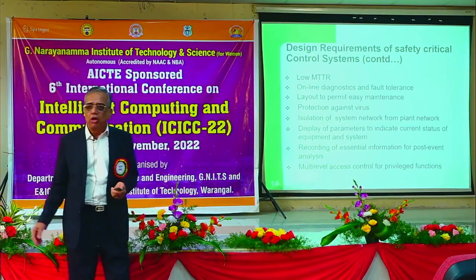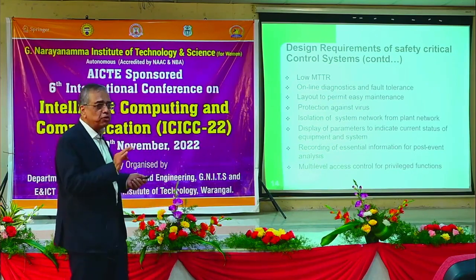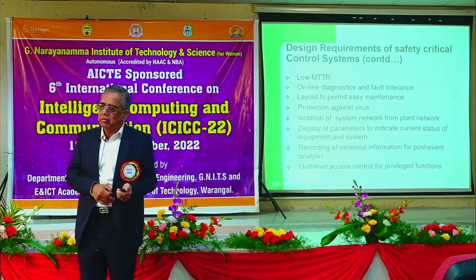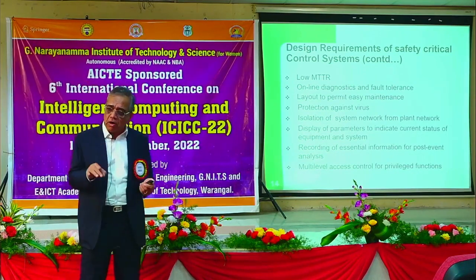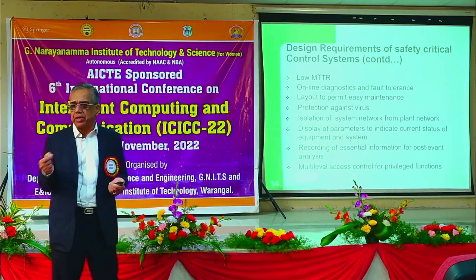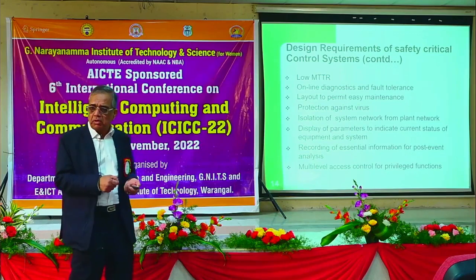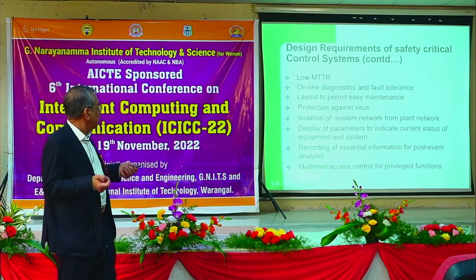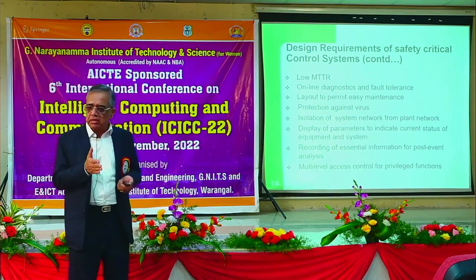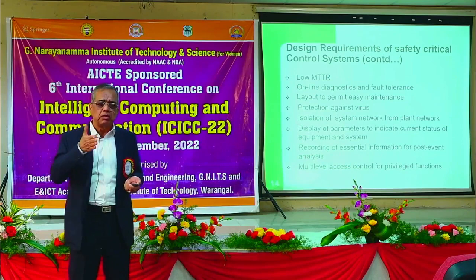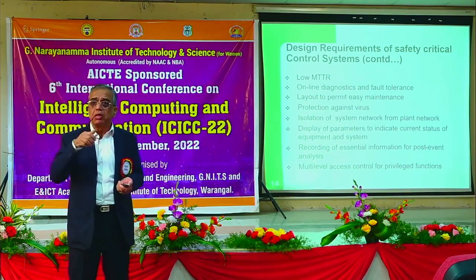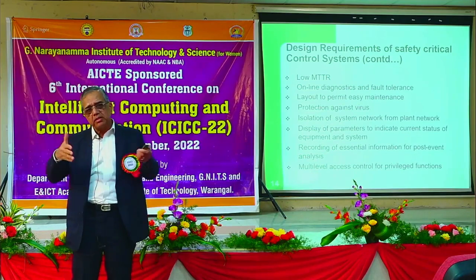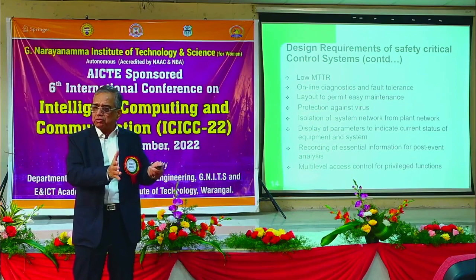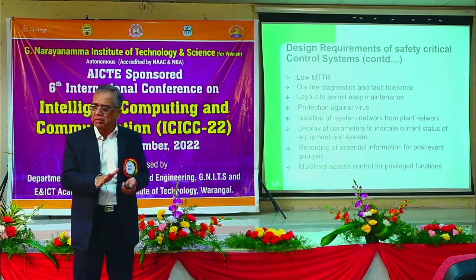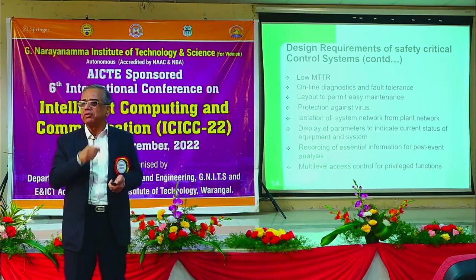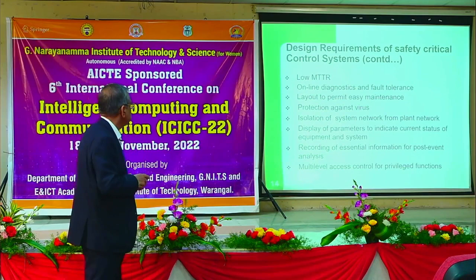Low MTTR, low mean time to repair. Now, how do you achieve low mean time to repair? First thing is that you must know there is a fault, you have to identify where the fault is, and you should replace those things immediately. To find the fault immediately, we use what we call online diagnostics, I will come back to that. To replace it, we must design in a way that it is just a matter of pulling out cards, it should not be a spread, it should be immediately put, and you must have tested spares available which can be immediately placed. And since it is a triplicated system, it is 2 out of 3, you can afford to switch off one system online, put it back and then do it. But we have designed a system where you do not have to switch off the power, you can directly do that. Those principles are also available.